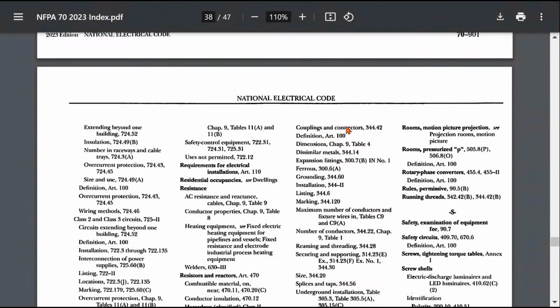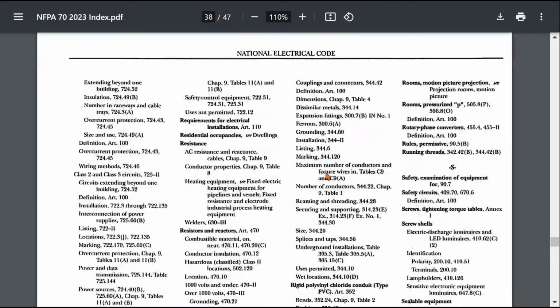344.42, couplings and connectors, dissimilar metals, something similar right there. So this is almost like a dissimilar metal situation. We've got aluminum fittings, and it's talking about connections. We're not talking about an aluminum enclosure, we're not talking about conductors, so that eliminates the conductors. Conduit, if you're going to use an aluminum fitting - so again, some of this stuff, you're thinking, let me look a little more here. Let's see here.